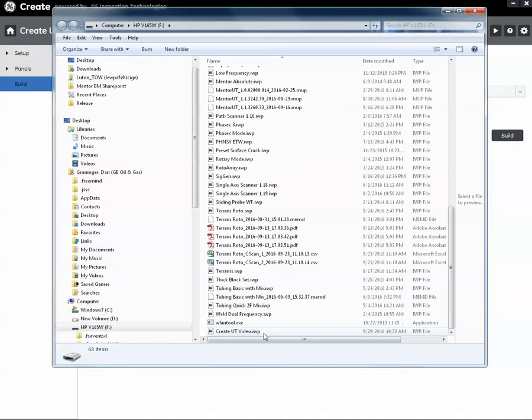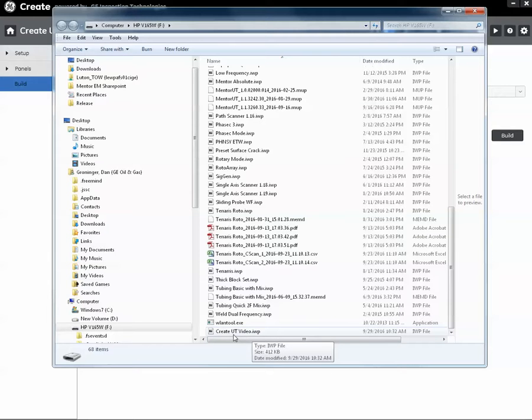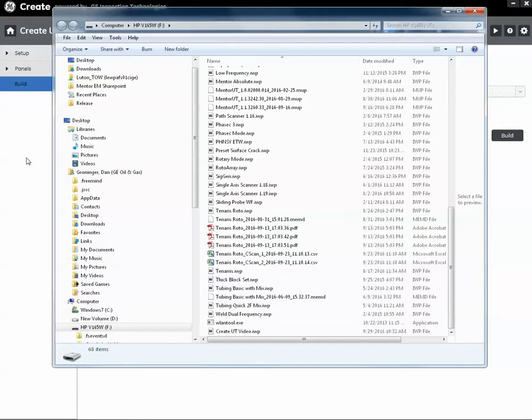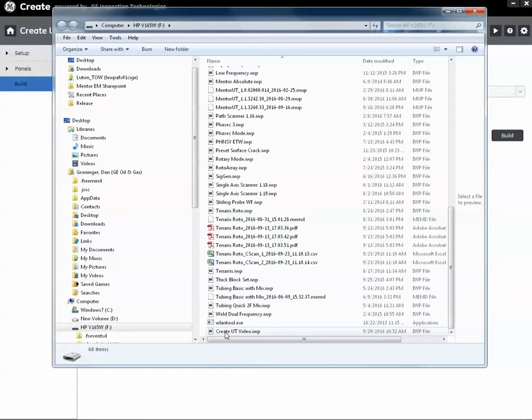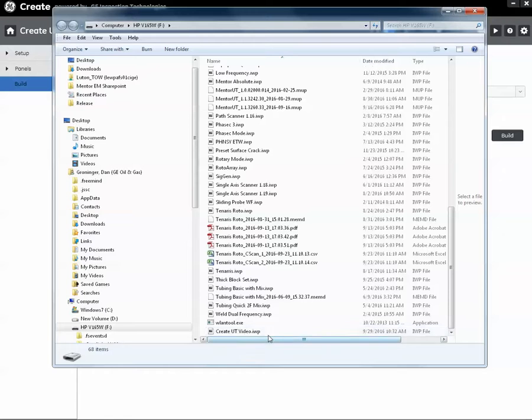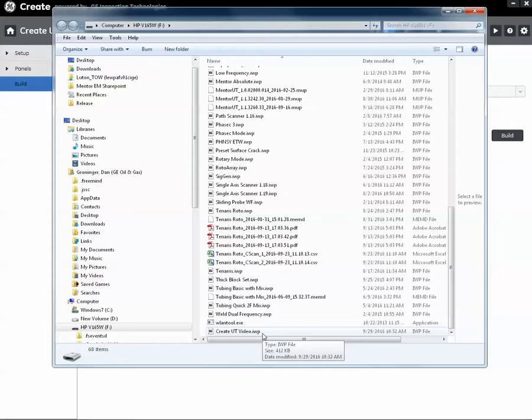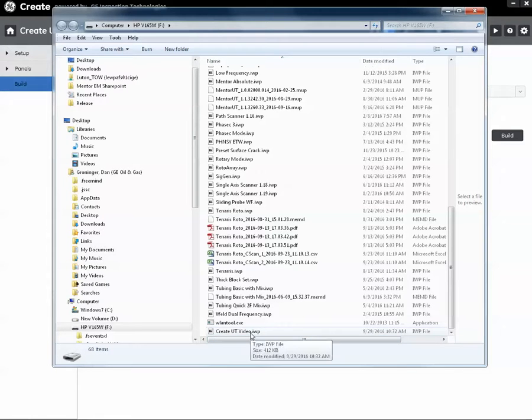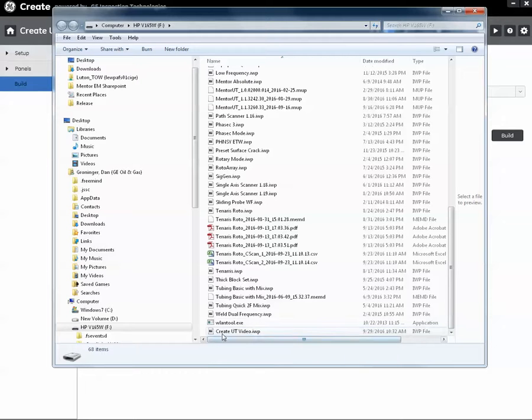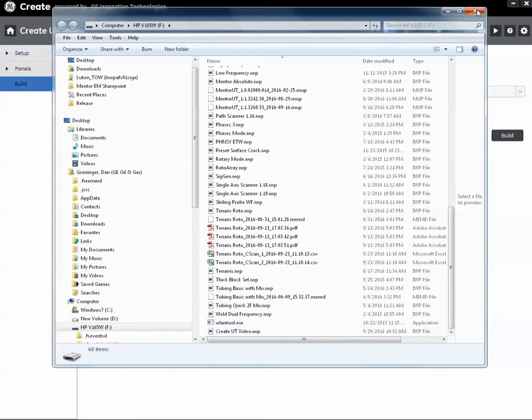One caution, do not rename these after they've been created. If you want to rename them, clone them in Create and rebuild the app with its new name. If you simply rename this file, it will get very confused when the app is installed on the instrument. And these files, the app files are compressed files that contain XML code for the app itself, along with all the videos, the PDFs, everything that you embedded in the app goes along with it. So there's a lot of information in that file that the instrument needs to unpack in a specific order. And if you just simply rename this file, it will confuse things.